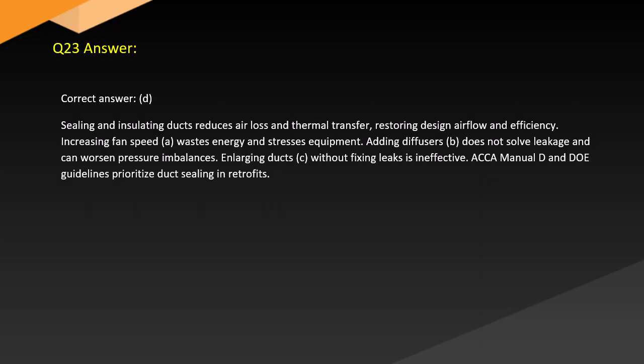Answer. Correct answer. D. Sealing and insulating ducts reduces air loss and thermal transfer, restoring design airflow and efficiency. Increasing fan speed, A, wastes energy and stresses equipment. Adding diffusers, B, does not solve leakage and can worsen pressure imbalances. Enlarging ducts, C, without fixing leaks is ineffective. ACCA Manual D and DOE guidelines prioritize duct sealing in retrofits.